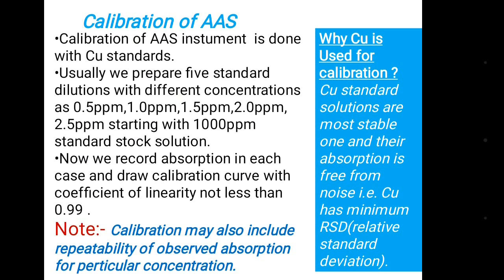The question arises: why do we use copper for calibration? Copper standard solutions are the most stable and their absorption is free from noise. That is, copper has minimum RSD (relative standard deviation). Note that calibration may also include repeatability of absorption at a particular concentration.